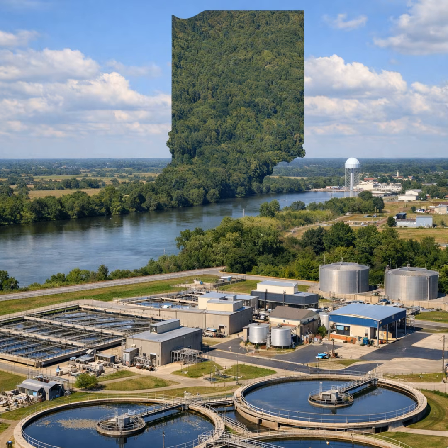So next we're going to jump to what is BOD, COD, and CBOD. BOD is biochemical oxygen demand. And biochemical oxygen demand represents the amount of oxygen consumed by bacteria and other microorganisms while they decompose organic matter under aerobic conditions at a specified temperature.